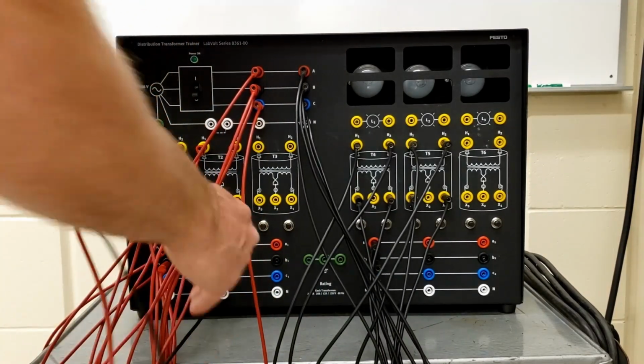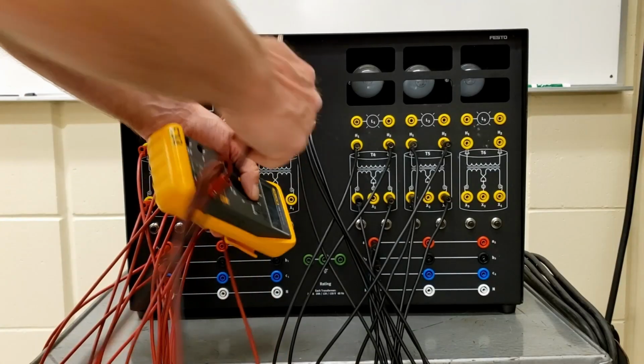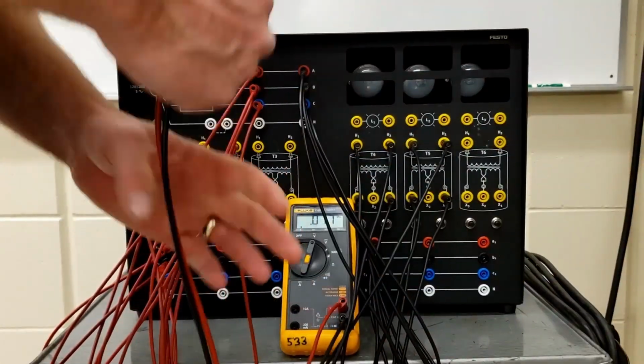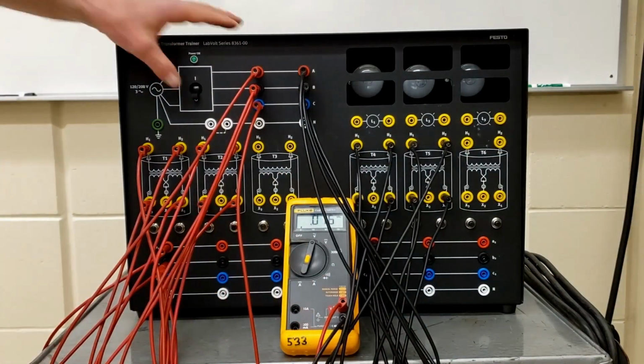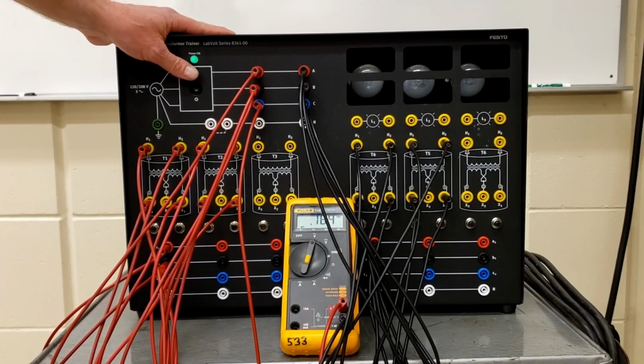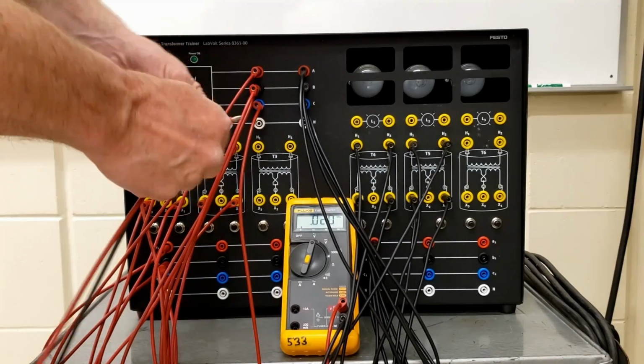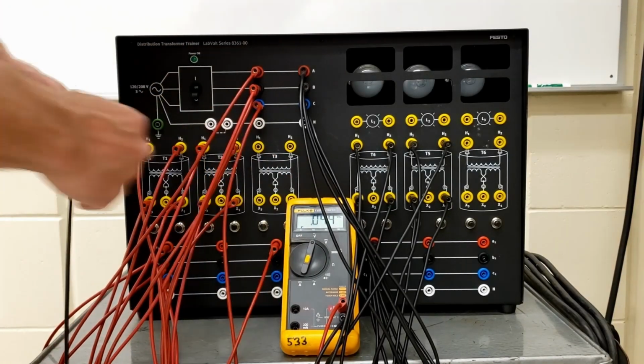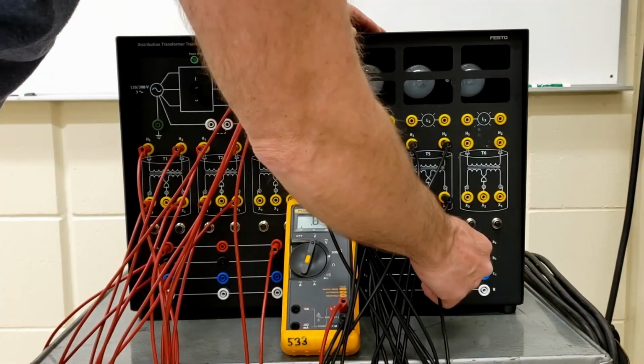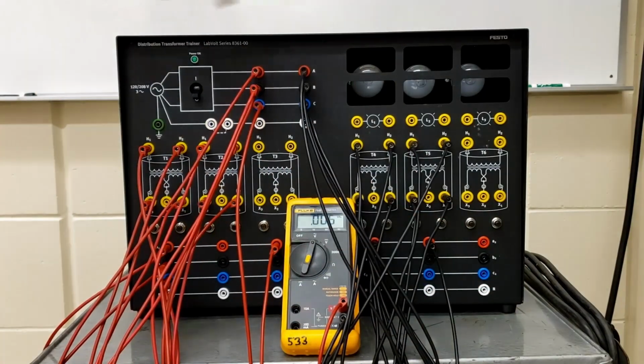Let's pull this bad boy out of that circuit there. Let's put it back here. Okay. Let's make sure that I haven't messed anything up. Okay, the breaker's holding. So I'm now going to test out the voltage between A1 and A2. So those 2 bus, those guys are both 0 degrees phase shift. So there should be virtually no voltage difference between those guys. So we got 7 volts difference between them, right?